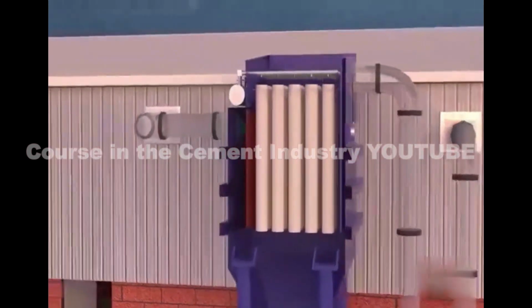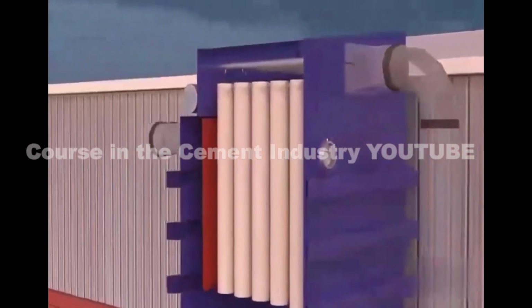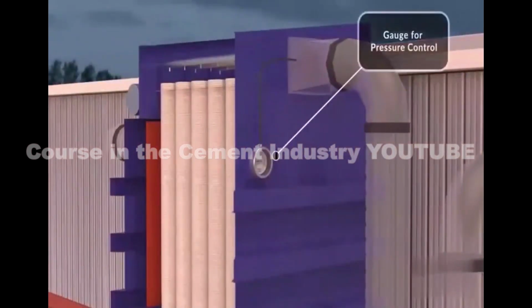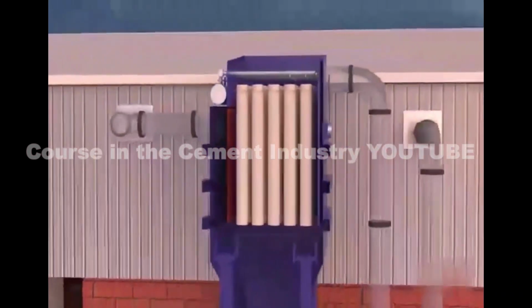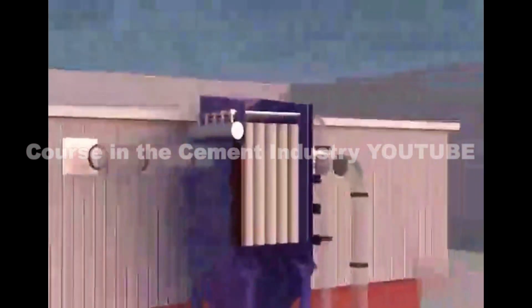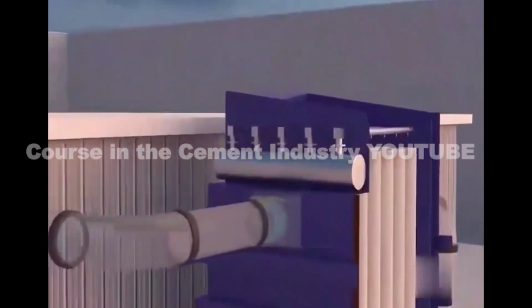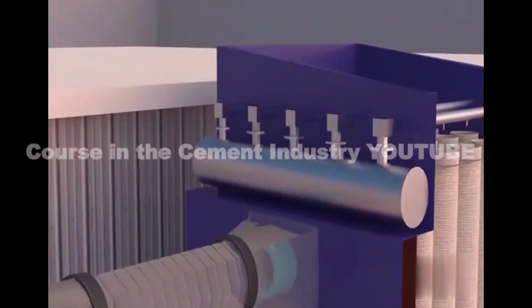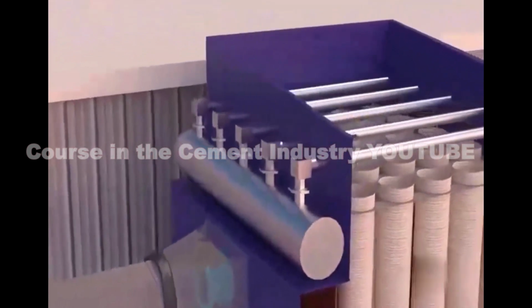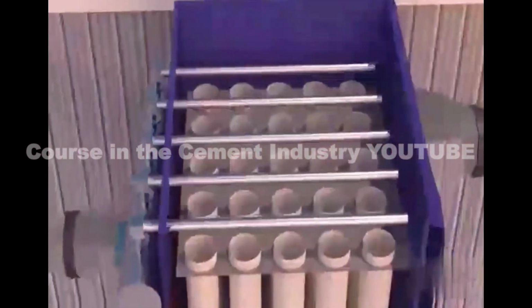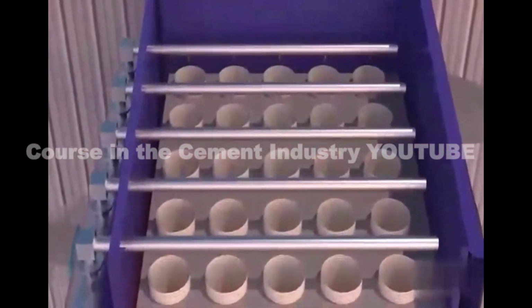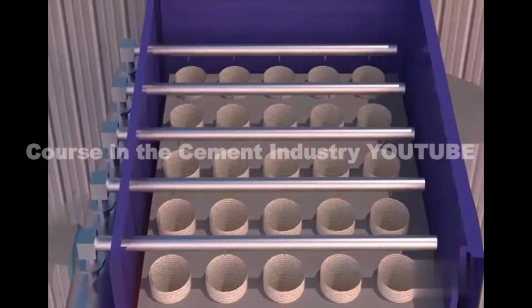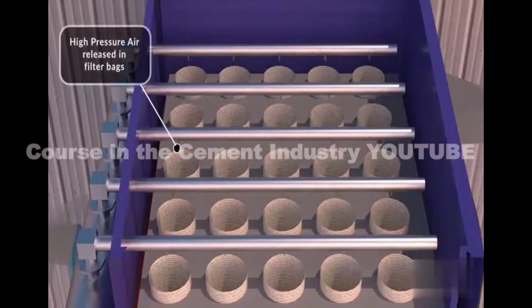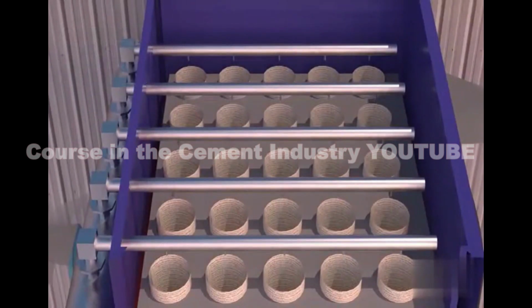When a certain level of deposit is reached on the filter bags, a pressure is created. This is detected by a gauge fitted on the machine, and this starts a process of cleaning of the filter bags. Air stored in the header is released, which is carried by the blowpipes. This high-pressure air is then released in the filter bags one row at a time. This air passing through the filter bags releases the deposited dust and cleans the bag. The dust then falls off into the hopper. This process takes place at regular intervals of time, and this allows the filtration to continue.